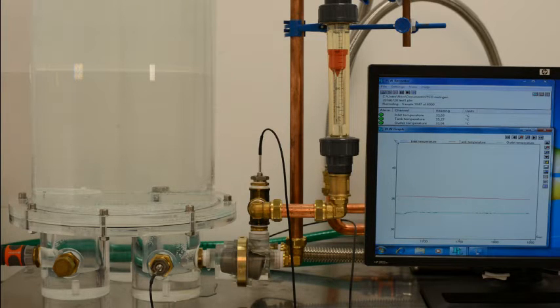So to give you a quick demonstration, at the moment there are no hot or cold taps running through the heat exchanger, so it's just running in a closed circuit, no heat being added or withdrawn, and you can see it's completely stable. What I'll start doing now is start adding some hot tap water or cold tap water to the heat exchanger to heat or cool the circuit, and then you will see the temperatures changing and the valve changing position.